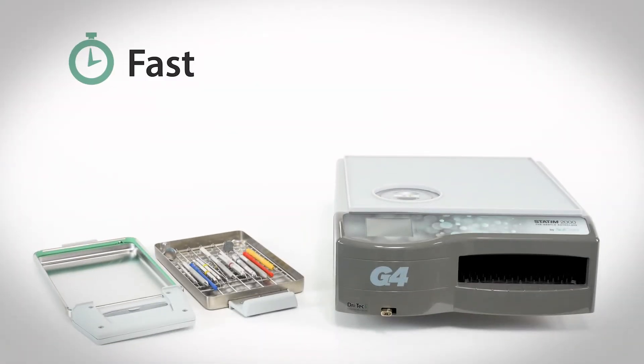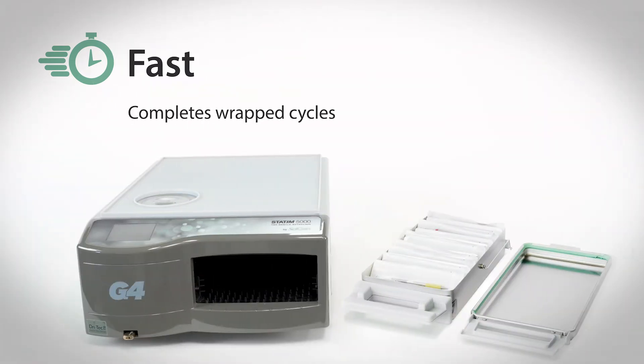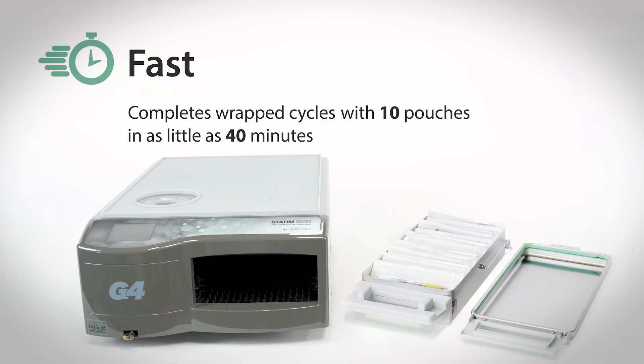The Statim sterilizes unwrapped instruments in as little as 6 minutes and completes wrapped cycles with 10 pouches in as little as 40 minutes.